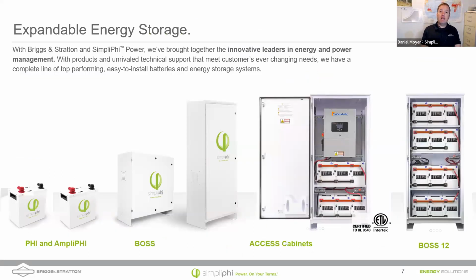PHI and AmpliPHI on the far left. The Phi battery is our standard non-communicating battery. The AmpliPHI battery has a digital battery management system with closed loop communications. So what does that offer you? A battery that can talk to an inverter, talk to a charge controller, automatically pre-populate set points, saving you time commissioning. A communicating battery can offer higher level protections. It can tell an inverter or charge controller what its state of charge is, or whether it's not being charged or discharged properly, and tell that equipment, hey, that's not right—let's treat me the correct way.